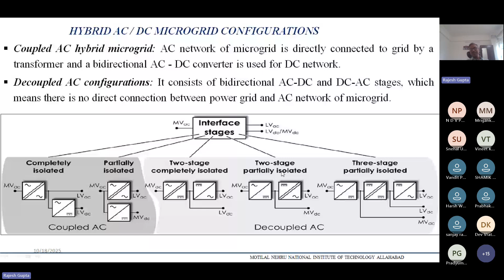Now, in general, as far as control of a microgrid is concerned, we have three hierarchical steps. It's not three classes, there are three hierarchies: primary control, secondary control, and tertiary control. Primary control is responsible for inner controls, exactly at the power electronics converter, like current control and voltage control.